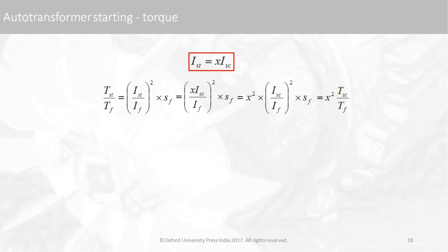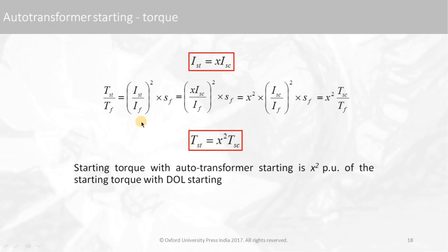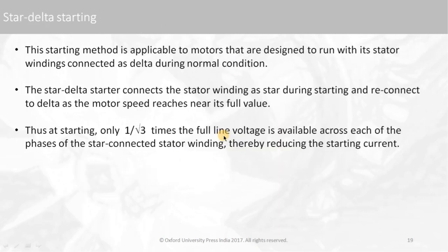The interesting fact is that the torque is also reduced by the factor x² compared to DOL starting. So the starting torque in auto transformer starting is x² per unit of the DOL starting torque. We must maintain the tapping such that the starting torque is not reduced so much that the motor fails to start. In DOL starting with six times short circuit current, the starting torque is 1.6 times the full load torque at 5% slip — whereas it reduces in the case of auto transformer starting.